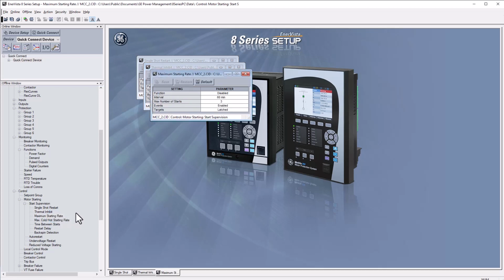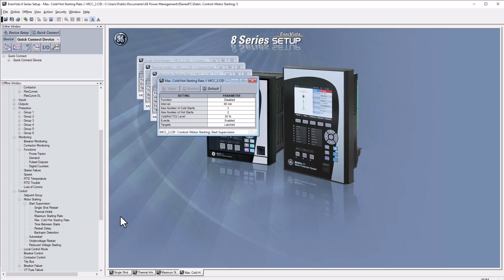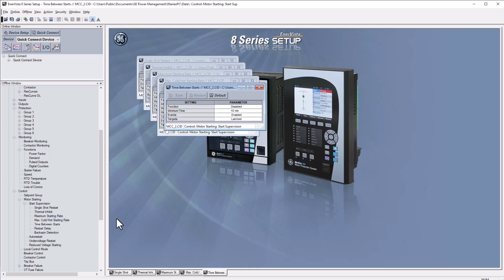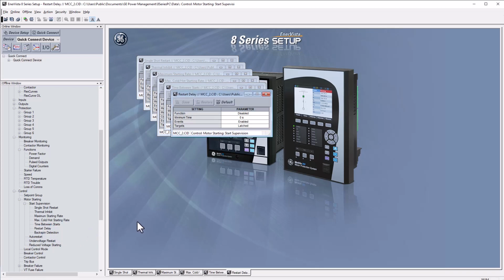Maximum starting rate defines the configurable number of start attempts allowed in a programmable time interval. Maximum cold hot starting rate defines the settable number of cold and hot start attempts allowed in a programmable time interval. Time between starts enforces a configurable minimum time duration between two successive start attempts. And the restart delay is used to ensure that a certain amount of time passes between the time a motor is stopped and restarting of that motor.